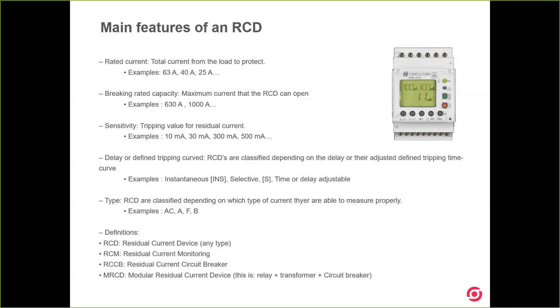Let's follow with the next concept, which is the breaking rated capacity — the maximum current that the RCD can open. Usually for residual current circuit breakers, the most typical examples are 630 amps, maybe 1000 amps. As you probably have seen, these are lower values compared to short circuits. RCDs do not protect against short circuits; the main functionality of RCDs is protection against leakage and residual currents. In case of a short circuit, the residual current device will not protect properly.